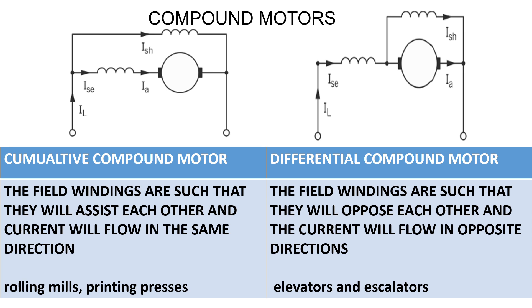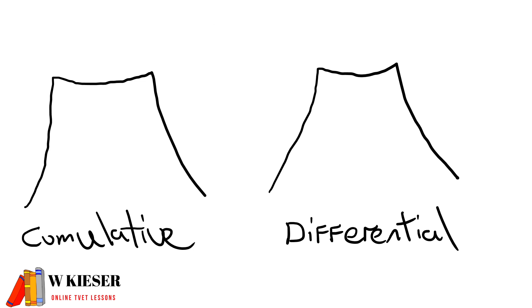Compound wound motors could either be cumulatively compounded or differentially compounded. If cumulatively compounded, the field windings assist each other and current flows in the same direction — these are used in rolling mills or printing presses. For differentially compounded motors, the field windings oppose each other and current flows in the opposite direction — these are used in elevators and escalators.